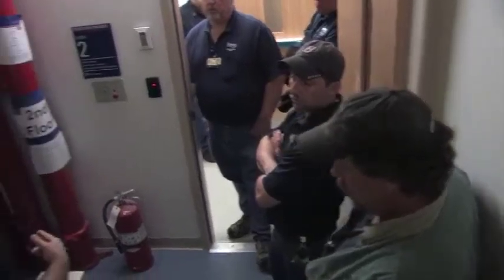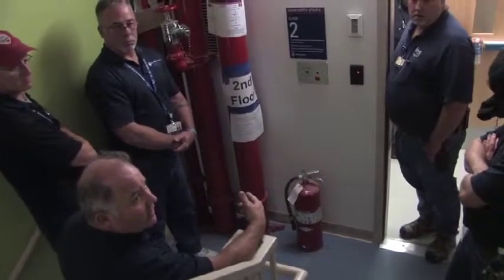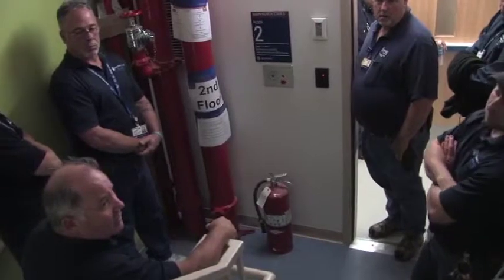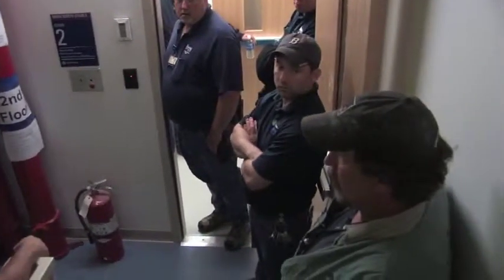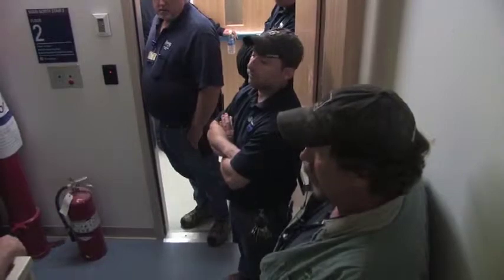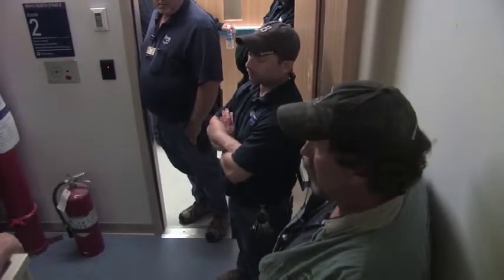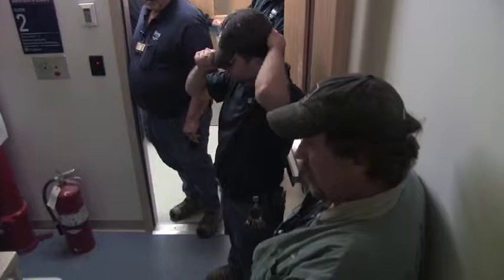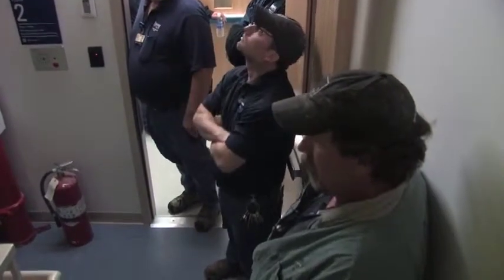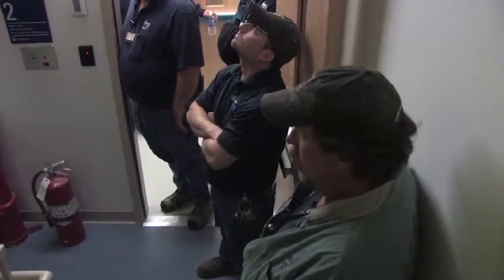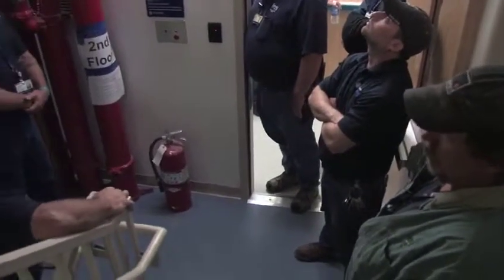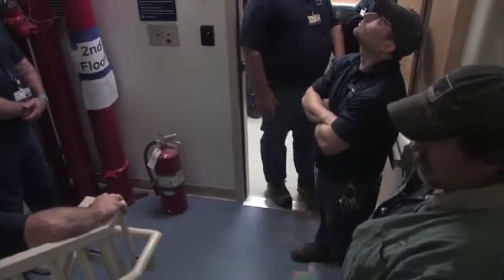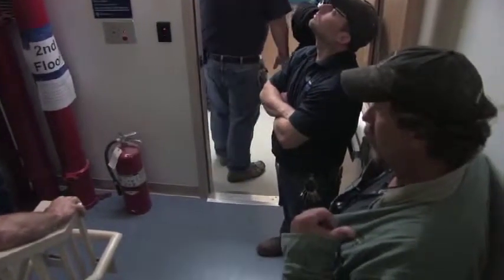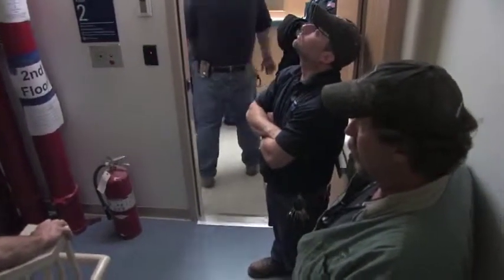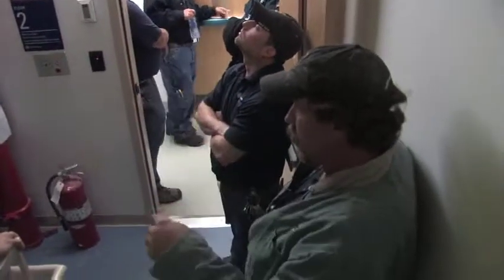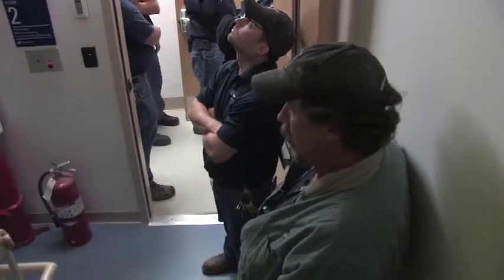On that pre-action, does it have drains, anything like that anywhere that we should know about? I don't think so. I think we got it pitching back pretty good. There's a low point drain on the valve. When it trips, there's a low point drain right there on the main valve. I don't think you're going to get that much water. Yeah, unless they had to go up and down under beams and stuff, but I don't think they did. I chased this one out pretty good. Yeah. And, well, you know, it does drop down, doesn't it? I'll take a look at that and find out.